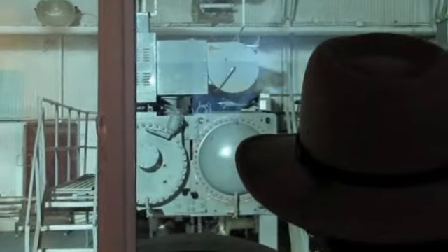Now once that steam has done its work for us, it comes back through the right tube, and in the winter we just open that up to our cold winter air. That's plenty cold enough to condense that refrigerant back to liquid form. During the summer we just put our cold creek water in there, and that condenses the refrigerant back to liquid form. Then we just reuse that same refrigerant over and over and over again. Now it's important to know that our refrigerant and our water never come in contact with each other. That way we're not polluting our water source whatsoever.